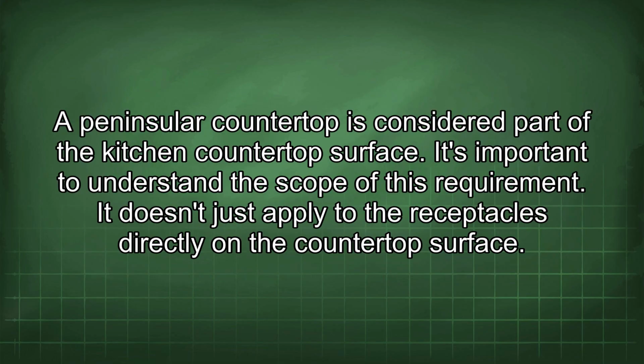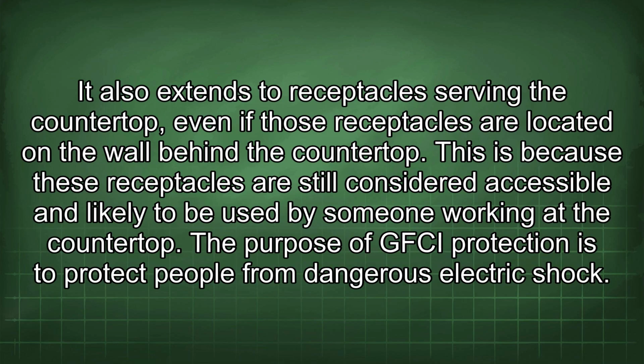A Peninsular countertop is considered part of the kitchen countertop surface. It's important to understand the scope of this requirement. It doesn't just apply to the receptacles directly on the countertop surface. It also extends to receptacles serving the countertop, even if those receptacles are located on the wall behind the countertop. This is because these receptacles are still considered accessible and likely to be used by someone working at the countertop.